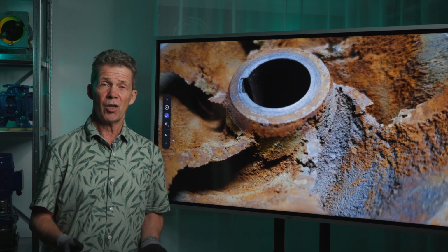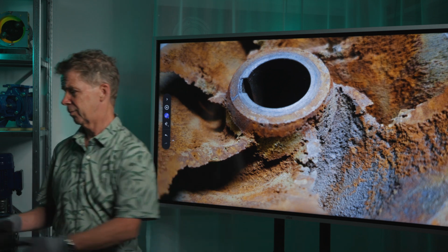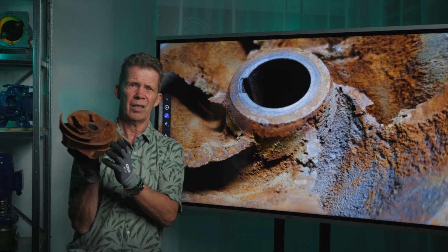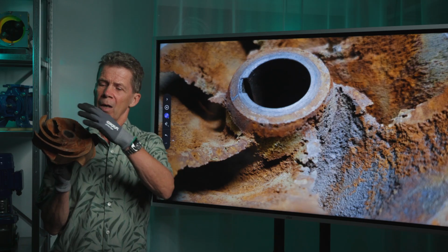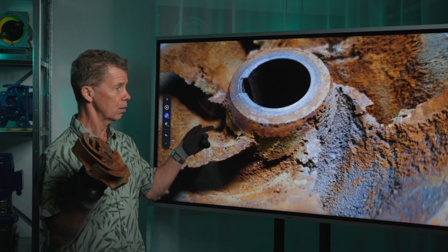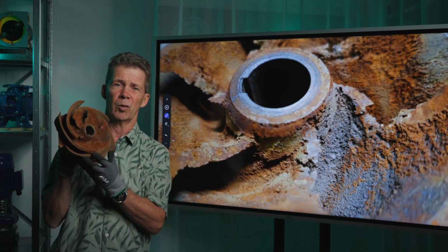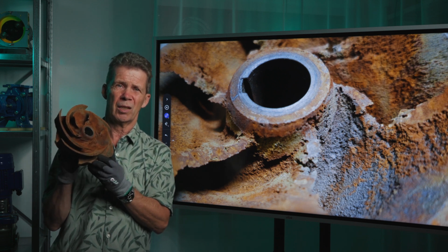The second example, if you deviate too much from BEP, is this impeller. I have it here. It's like a piece of art. This impeller was in a washing pump for a beet factory. This impeller is damaged. You see it also here on the picture on the board. This pump was only 6 months in operation. Failure mode is called cavitation.